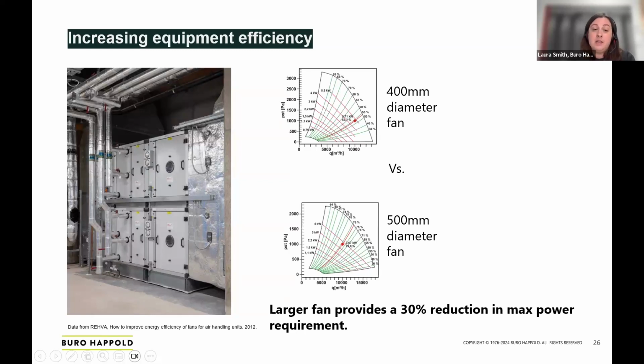One of the key components is the fan, and there are two fans, one to supply air into the building, one to extract air from it. If we compare a 400 millimeter diameter fan to a 500 millimeter one, with the same flow rate and resistance requirements, that 100 millimeter difference in fan size, because of the physics and the square law involved, means the larger fan provides a 30% reduction in maximum power requirement.